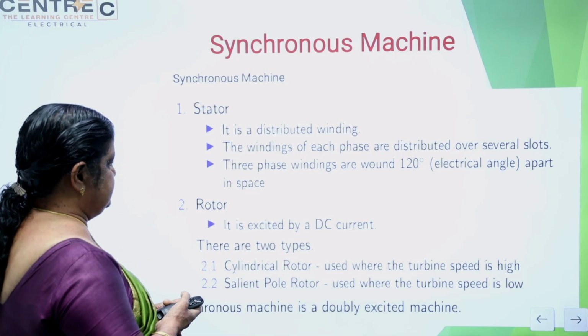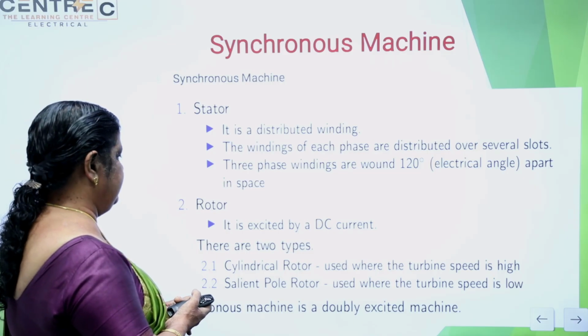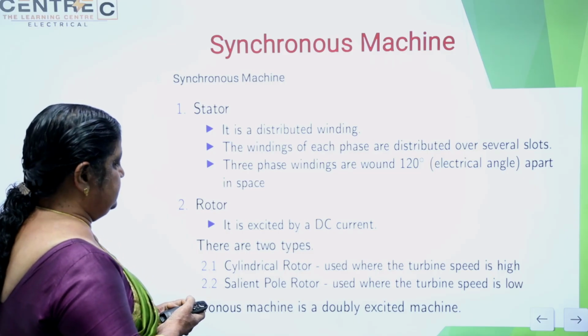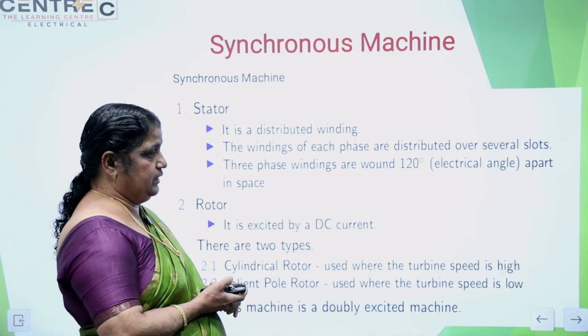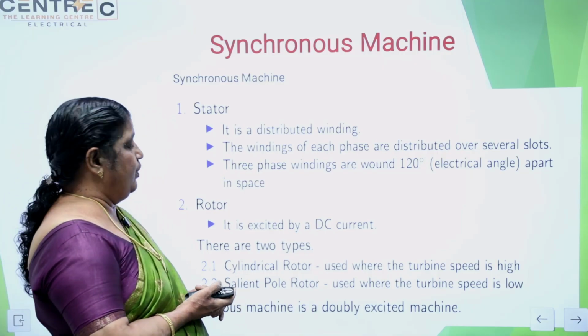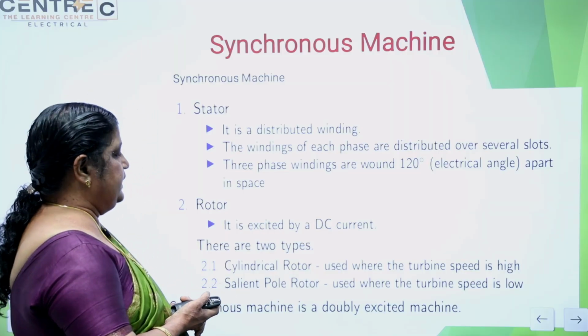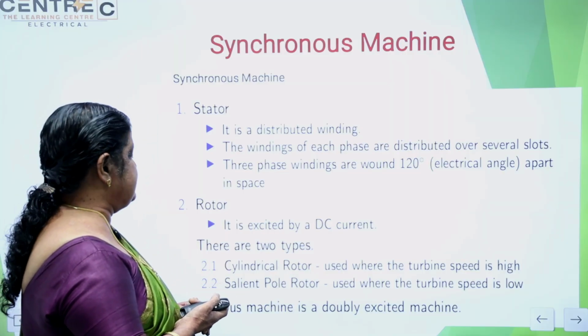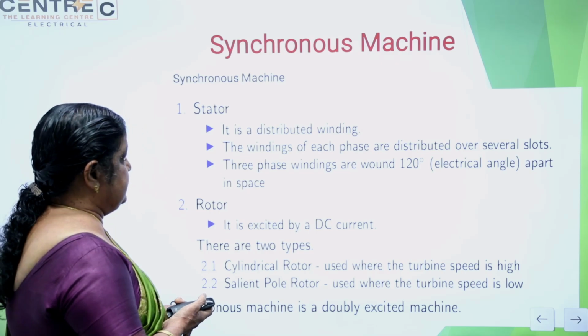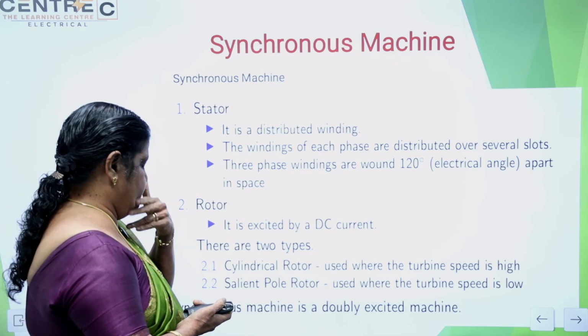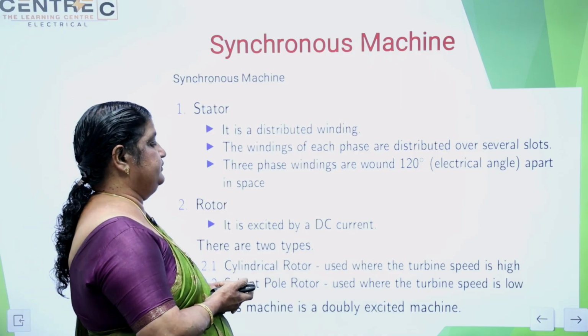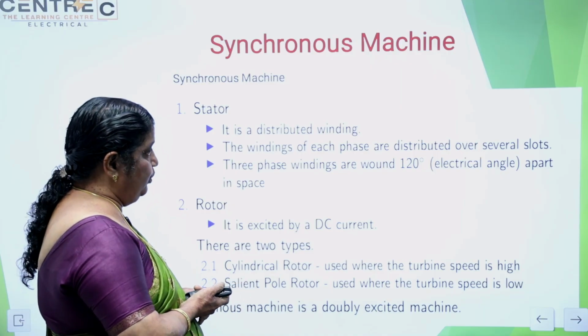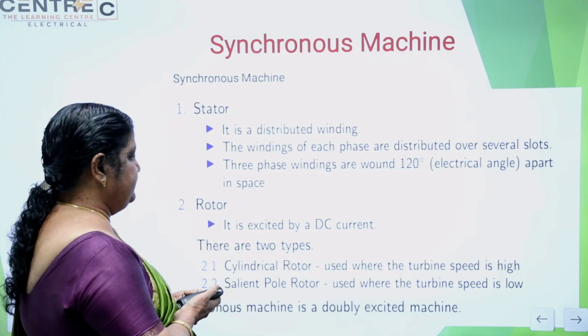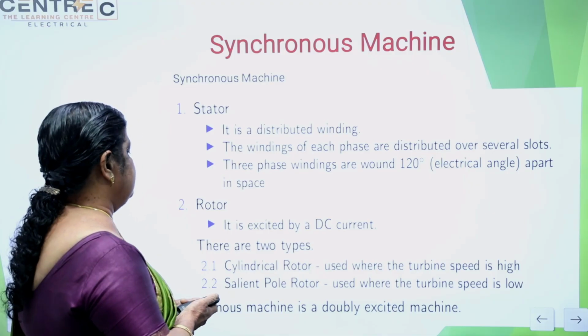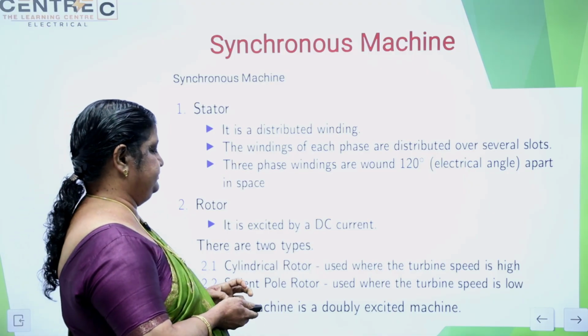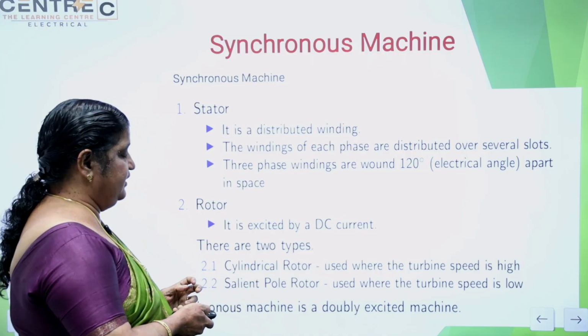Then the rotor is also a distributed winding. It is excited with DC current. Then, as per the rotor construction, there is the cylindrical rotor or salient pole rotor. In generators, salient pole rotor machines are mainly used in hydroelectric power plants, where the speed is very low, always less than 500. If the turbine speed is high, we can use a cylindrical rotor. It is a doubly excited machine, the synchronous machine.